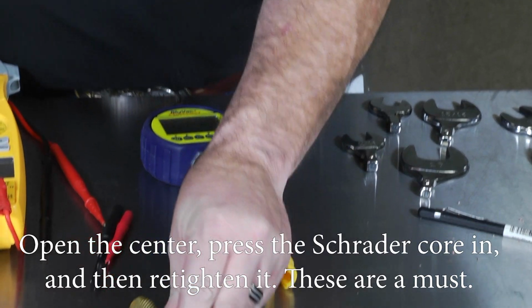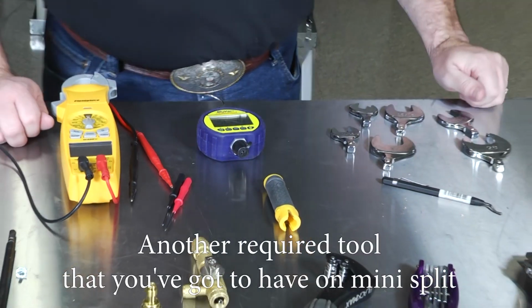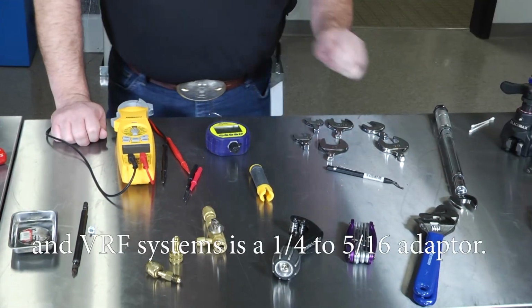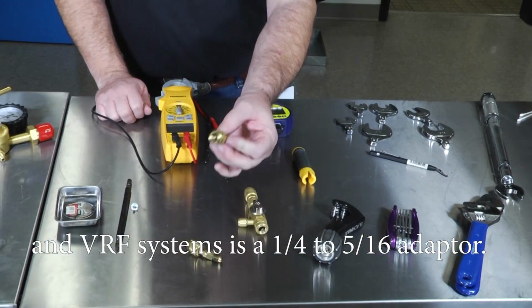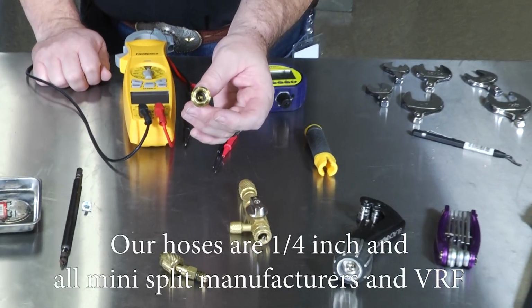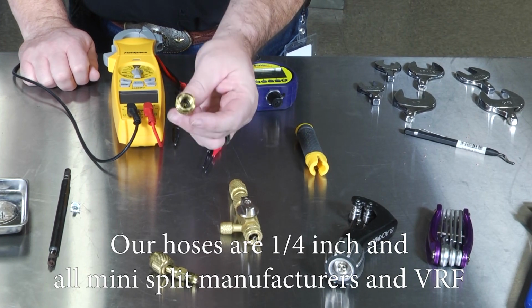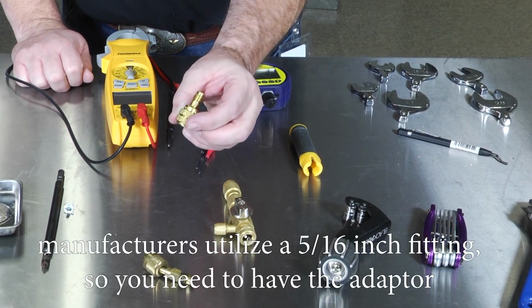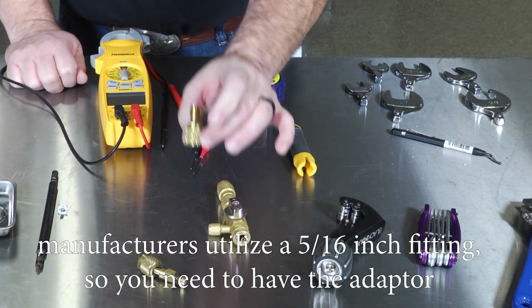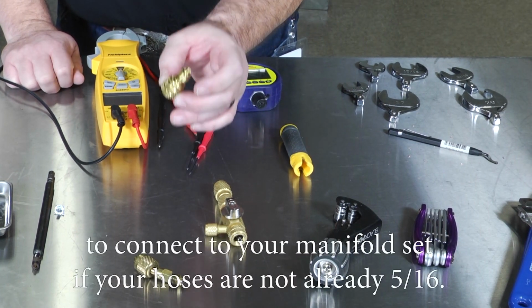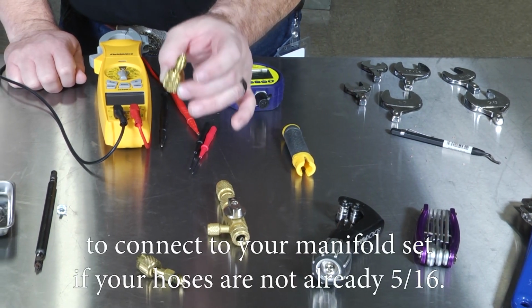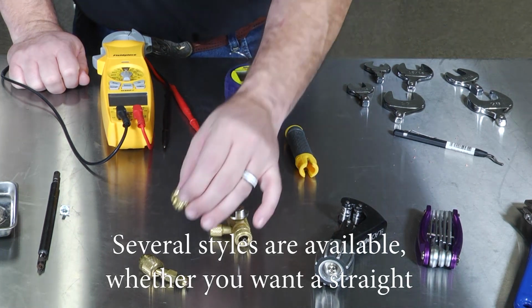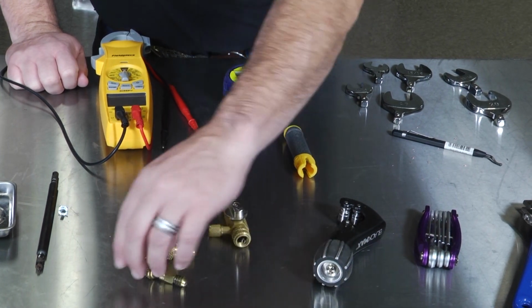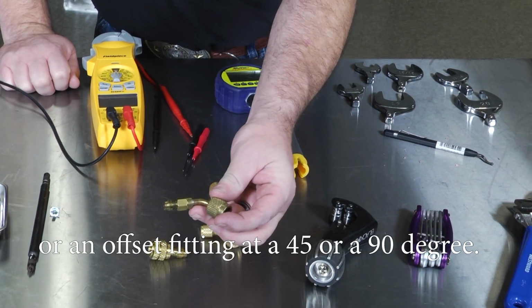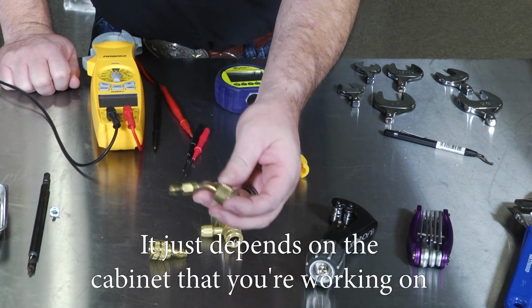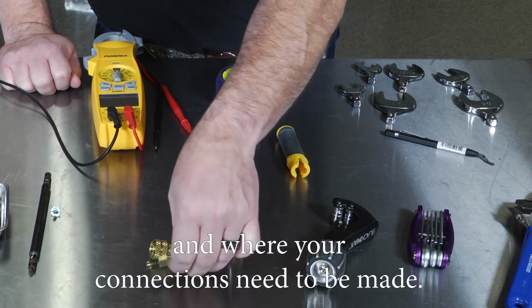These are a must. Another required tool that you've got to have on mini split and VRF systems is a 1/4 to 5/16 adapter. Our hoses are 1/4 inch, and all mini split manufacturers and VRF manufacturers utilize a 5/16 inch fitting, so you need to have the adapter to connect to your manifold set if your hoses are not already 5/16. Several styles are available, whether you want a straight or an offset fitting at a 45 or a 90 degree. Just depends on the cabinet that you're working on and where your connections need to be made.